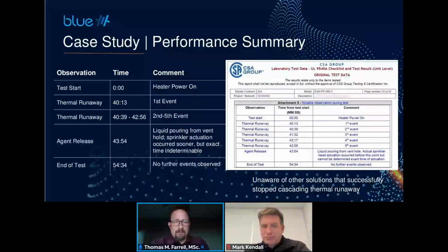Because of our approach with this particular agent, it's not an inert gas. It's not a sprinkler system. It's not an aerosol. It's not a flood with water. It's been acknowledged at this point by certain NFPA committees, most notably NFPA 855, that this is a novel way to approach these, not as fire suppression or as thermal runaway cessation, even though, as we've just shown here, that is possible. They acknowledge that it is a thermal runaway management solution, because that's what it's doing. It's managing the heat load from a thermal runaway event.